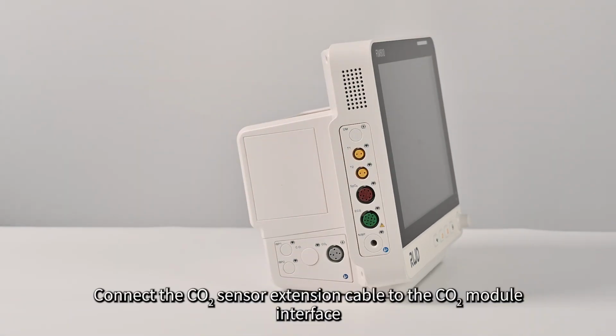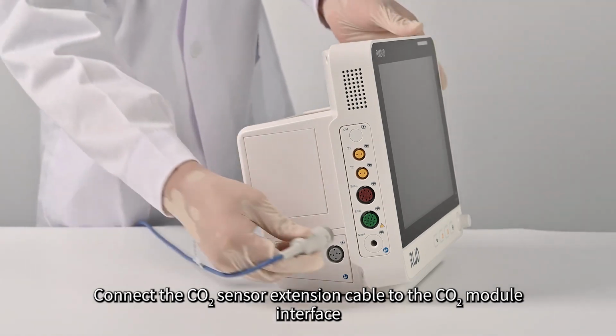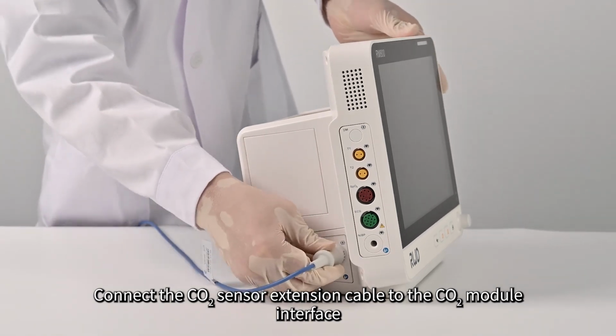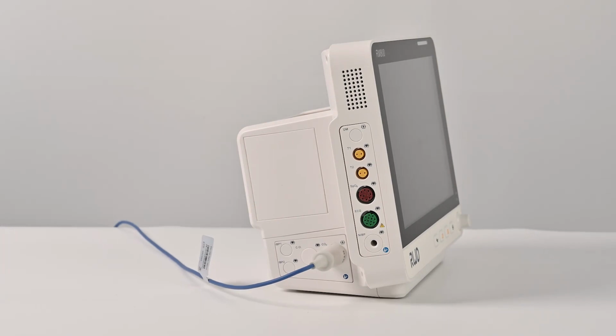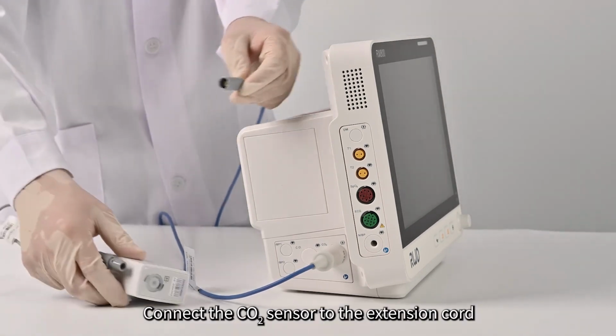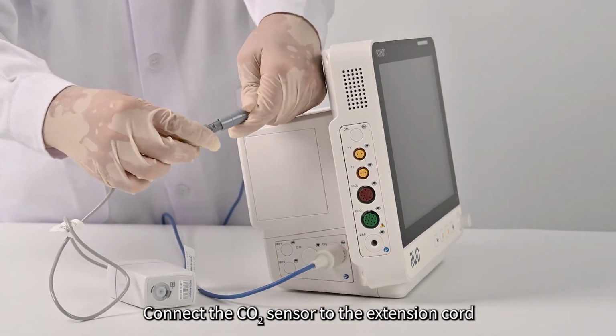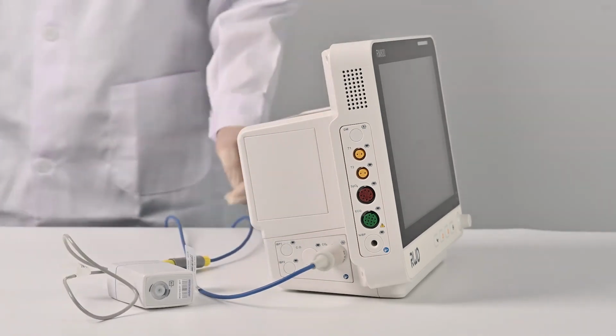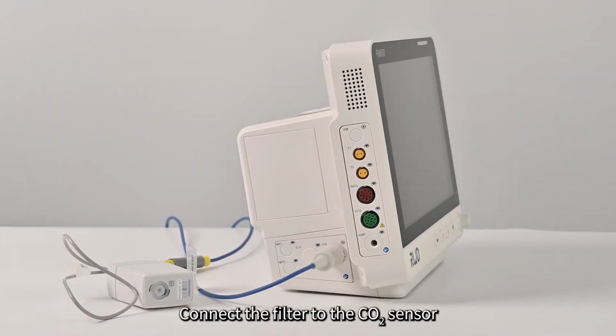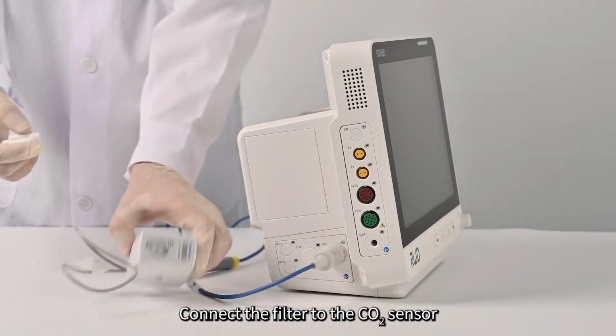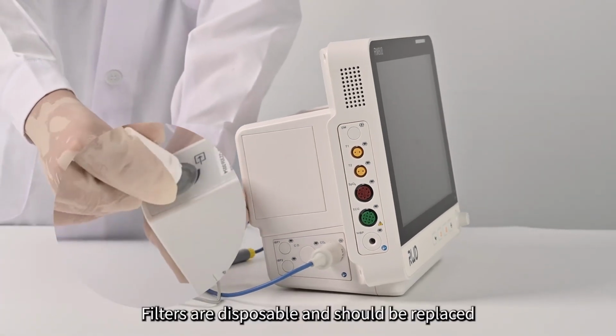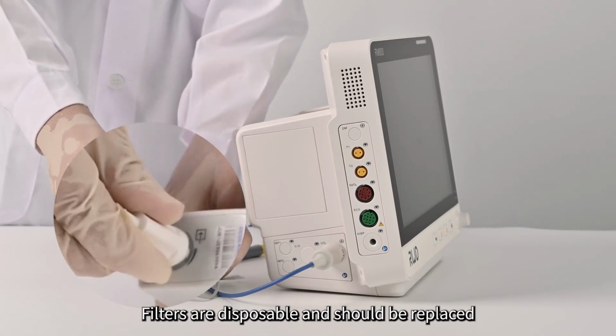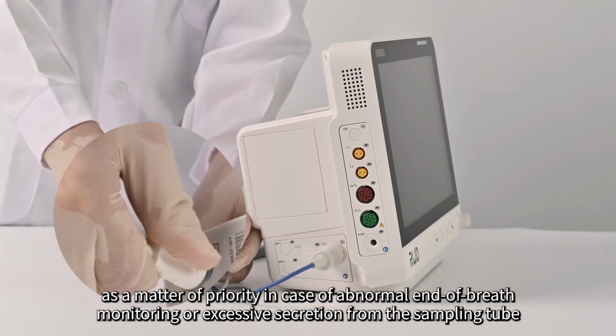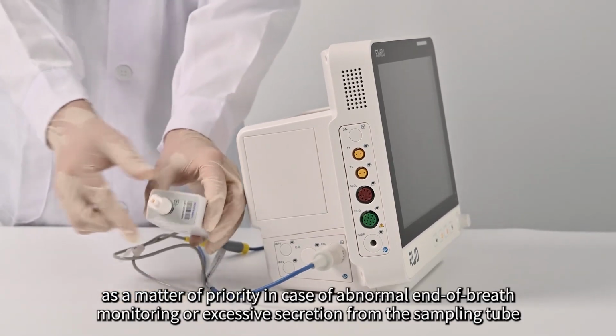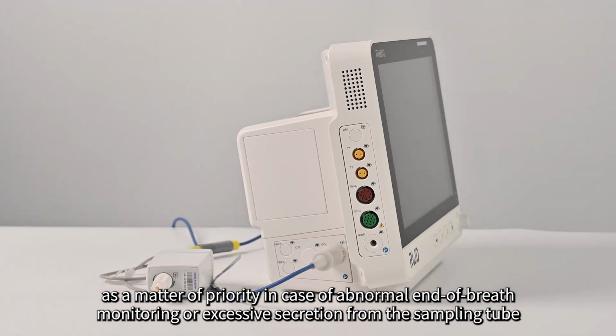Connect the carbon dioxide sensor extension cable to the carbon dioxide module interface. Connect the carbon dioxide sensor to the extension cable. Connect the filter to the carbon dioxide sensor. Filters are disposable and should be replaced as a priority in case of abnormal end-tidal monitoring or excessive secretion from the sampling tube.